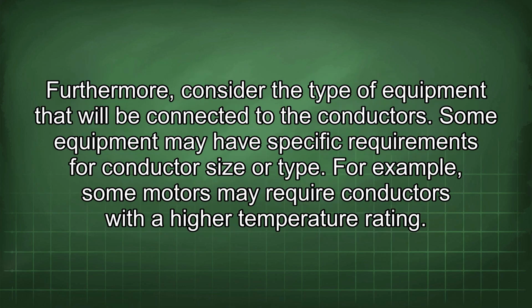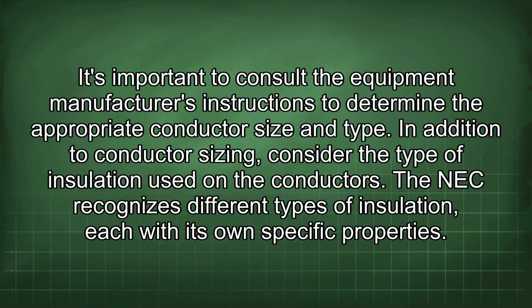Furthermore, consider the type of equipment that will be connected to the conductors. Some equipment may have specific requirements for conductor size or type. For example, some motors may require conductors with a high temperature rating. It's important to consult the equipment manufacturer's instructions to determine the appropriate conductor size and type.